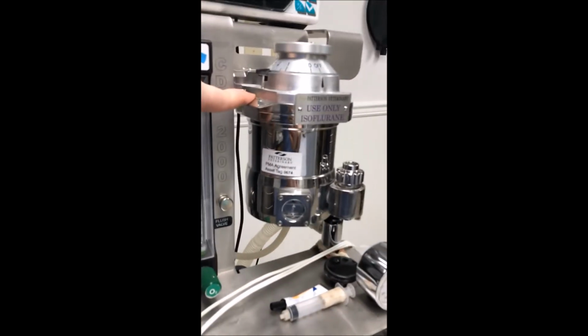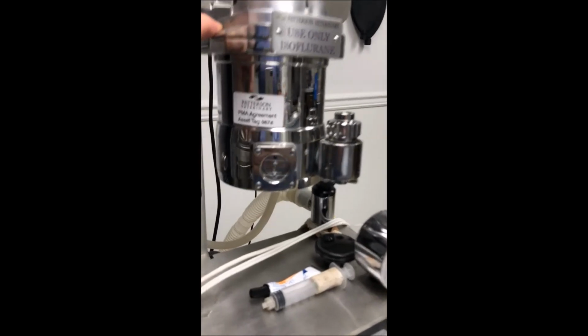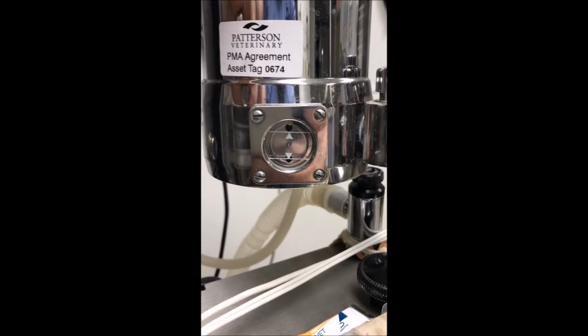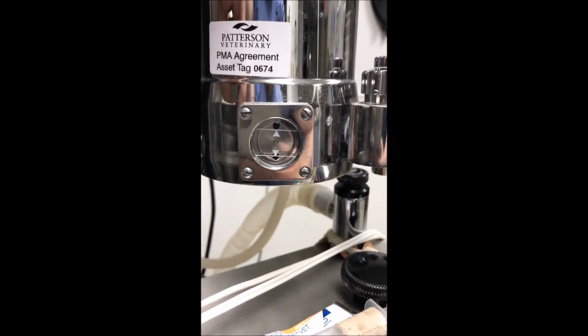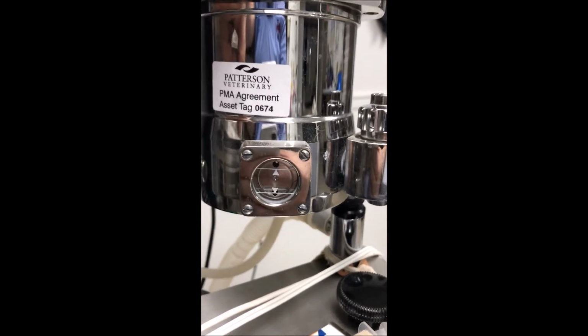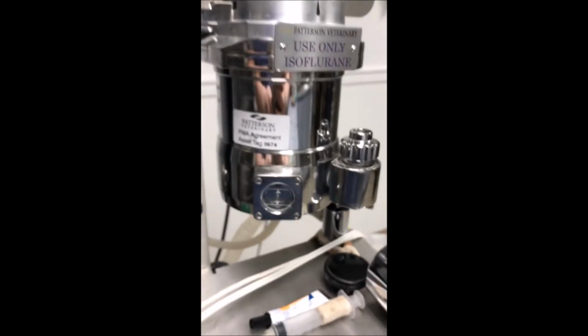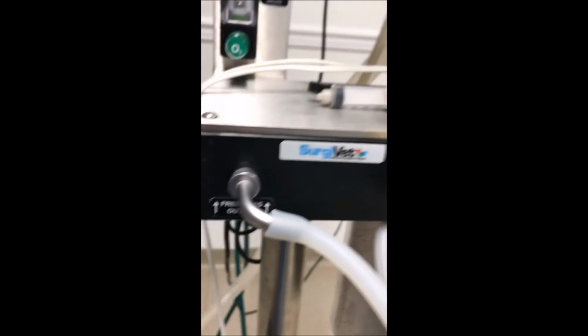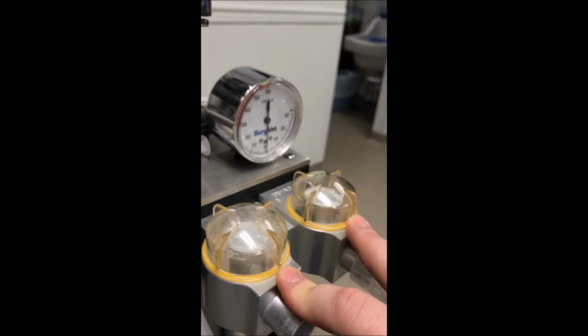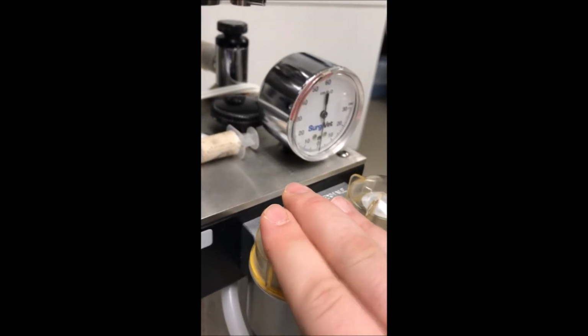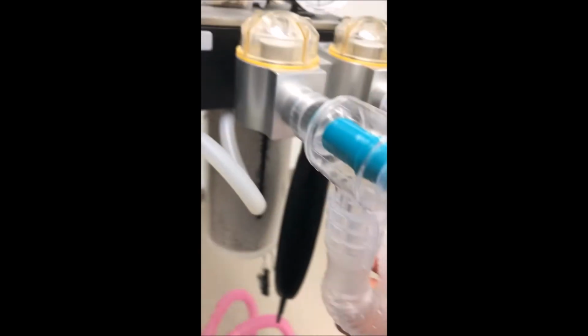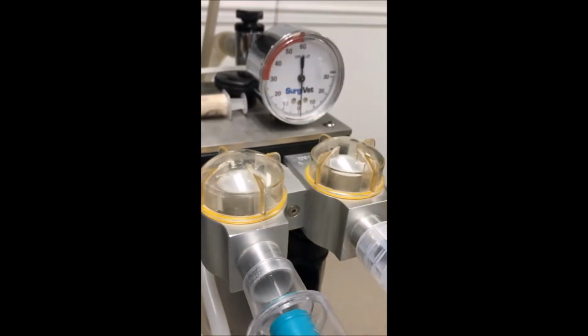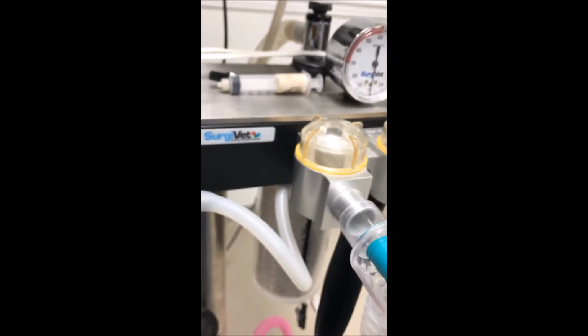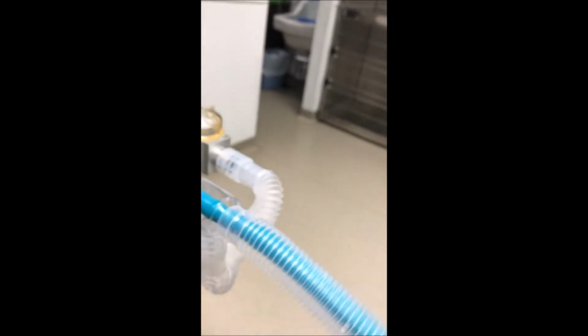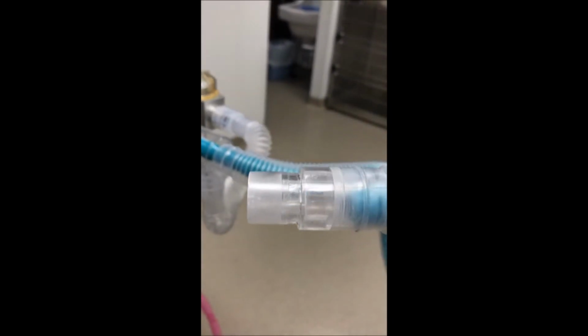We use isoflurane. Before we do any sort of procedure, we always need to check the level of our isoflurane. And as you can see, this is getting a little low, so we're gonna refill that before we put any patient on it. Once it leaves the isoflurane vaporizer, it comes out into our fresh gas outlet. This outlet leads to these unidirectional valves. The first valve is for inhalation. We have a Y circuit connected here. So air comes out this way, and then the patient is hooked up to this tube here, right there.